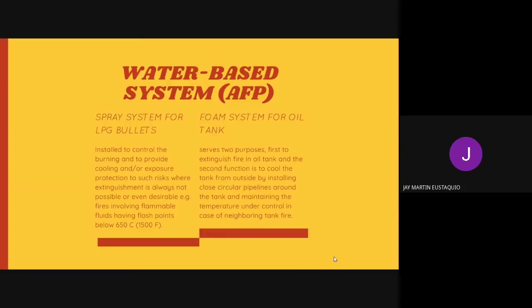So doon lalabas yung tubig para for cooling doon sa tank. Last is foam system for oil tank. Serves two purposes: first, to extinguish fire in oil tank, and second, to cool the tank from outside by installing closed circular pipelines around the tank and maintaining the temperature under control in case of neighboring tank fire. Itong foam system na to ay makikita lang din sa mga hazardous or high-risk areas.